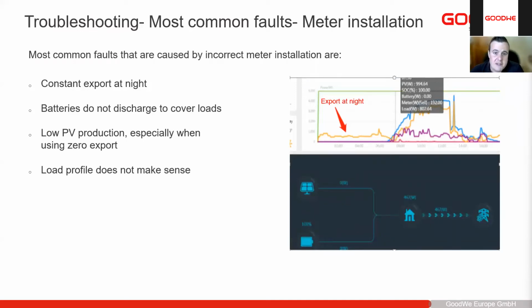Next is our meter installation. That's why phase order fault is before this. Very often, I'll show the next example, it happened exactly because of that. So this is a single phase device. You'll see export at night, no battery discharge, figures that don't make sense. That normally indicates a smart meter is installed incorrectly.